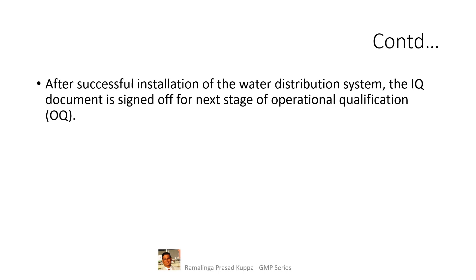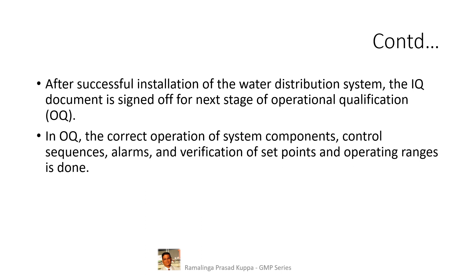After the IQ document is signed off, operate the system to check whether the operation meets the requirements. OQ is mostly operational checks of the system. During this OQ check, certain chemical and microbial parameters may be evaluated for compliance. In OQ, the correct operation of system components, control sequences, alarms, and verification of set points and operating ranges is done. When all these things are done successfully, the OQ document should be signed off.